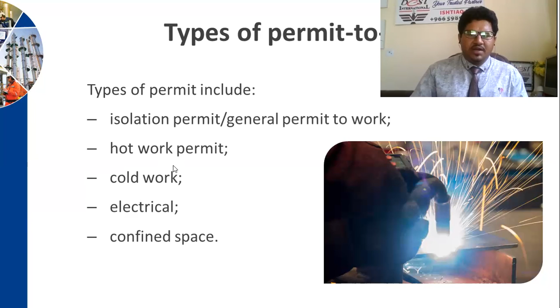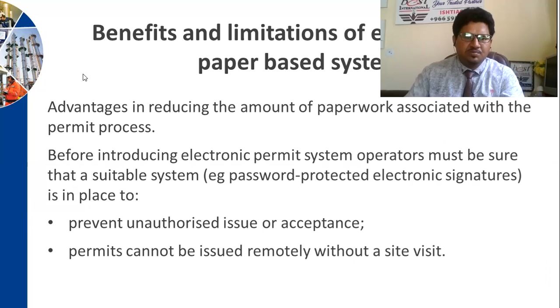Now remember, what are the benefits and limitations of electronic and paper-based systems? Advantages include reducing the amount of paperwork associated with the permit process. Before introducing an electronic system, operators must be sure that a suitable system, such as a password protected electronic signature, is in place to prevent unauthorized use or acceptance, that permits cannot be issued remotely without a site visit, and that permits already issued cannot be altered without the alteration being communicated to all concerned.